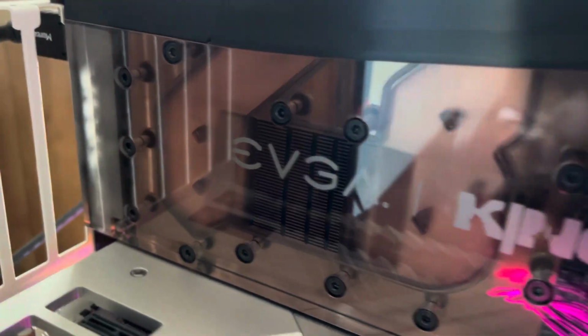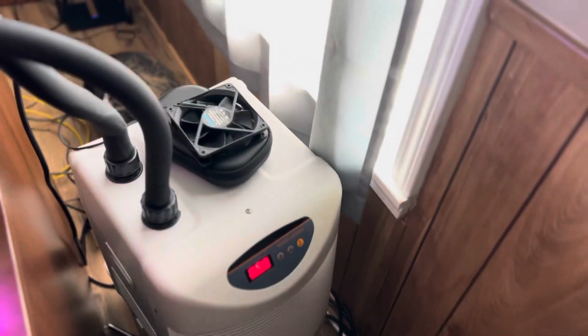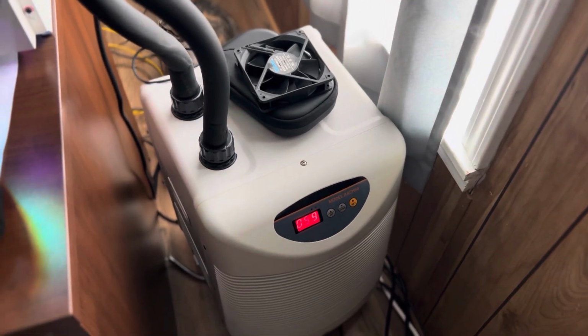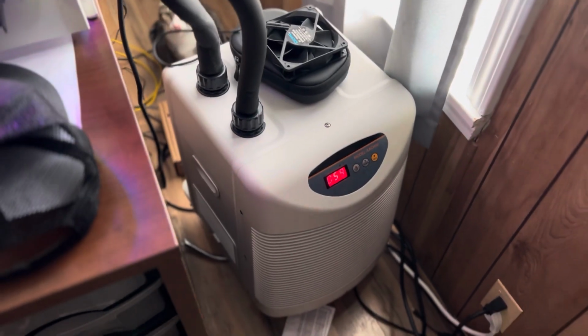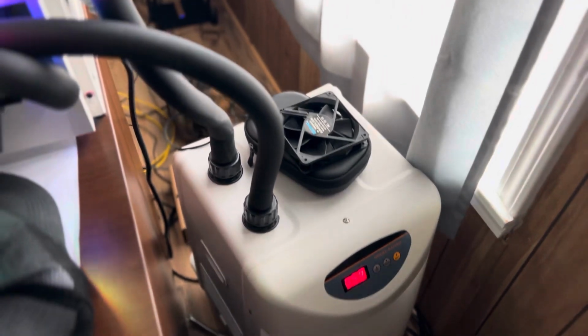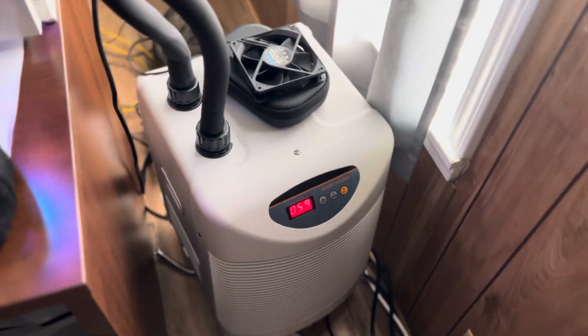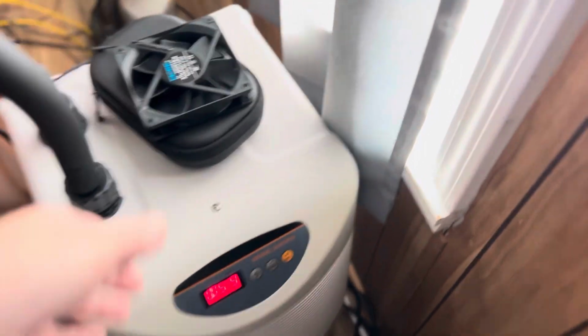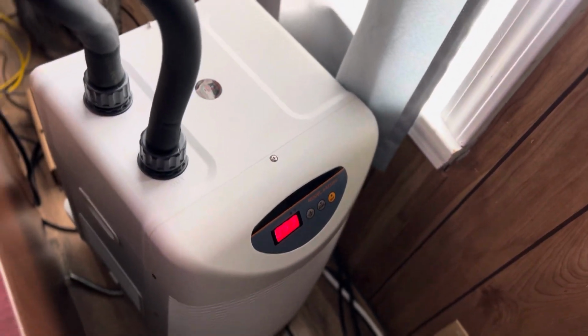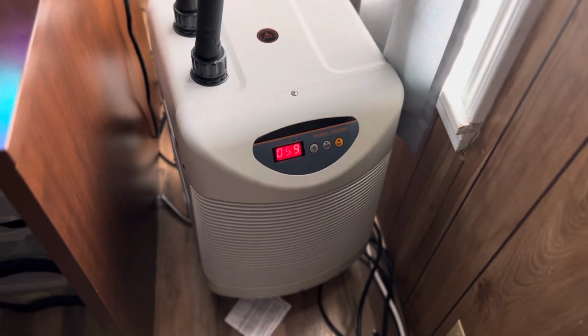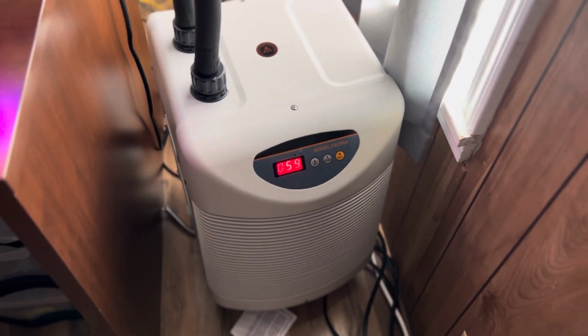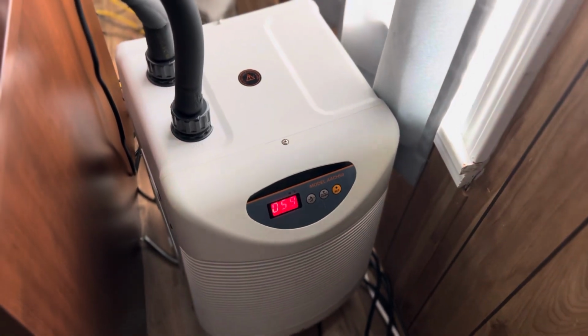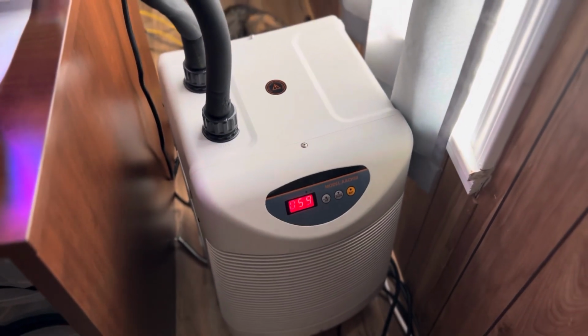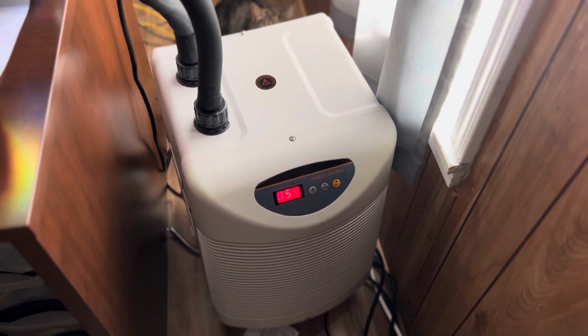With all of these components heating up this liquid, the water is going to reach a warmer point faster than your chiller can realize it needs to kick itself back on. So what ends up happening is your water chiller temperature will actually exceed where you want it to. So if you set it to 15 Celsius, you're playing a game, your water warms up to 16, 17, 18, even 19 Celsius, and the chiller's like, oh wait, we got to turn back on.